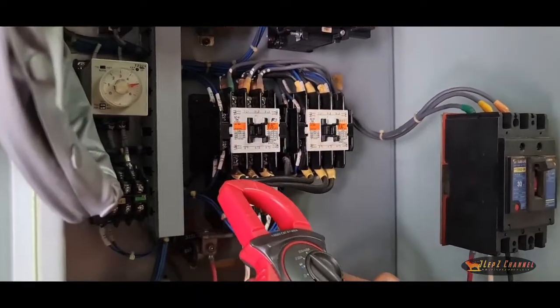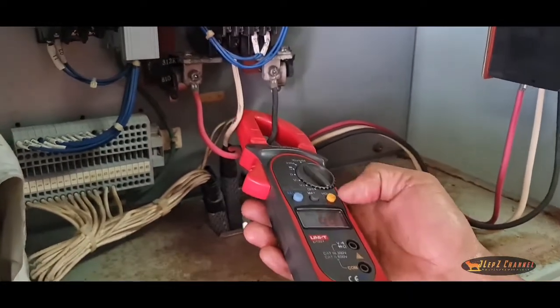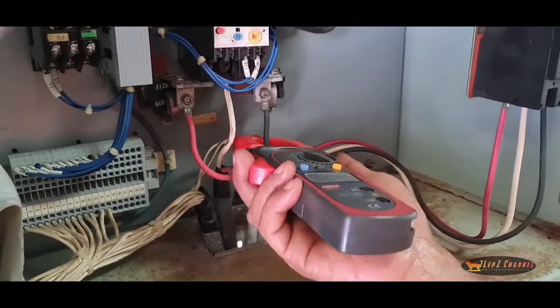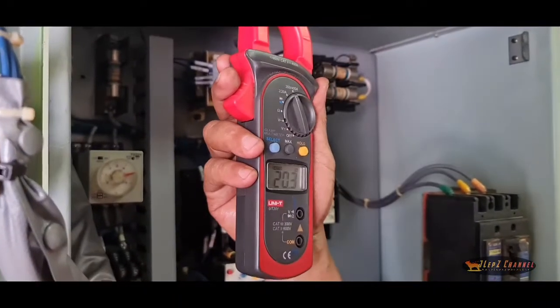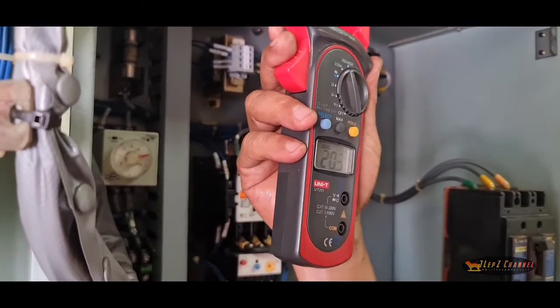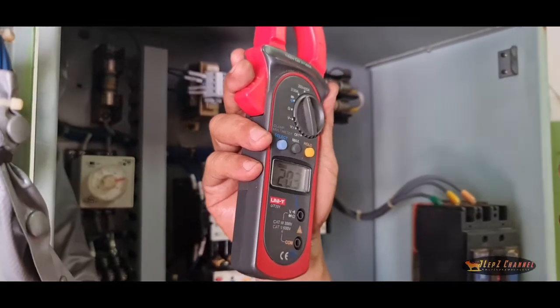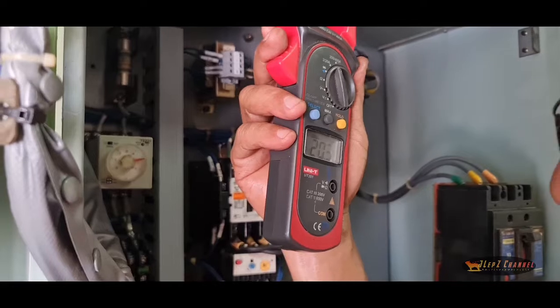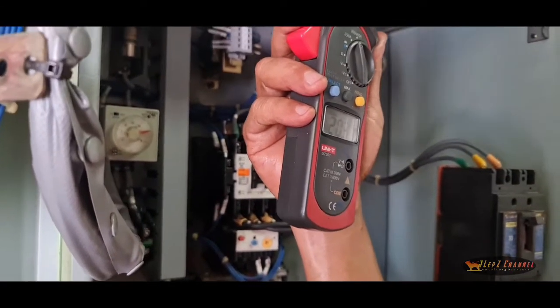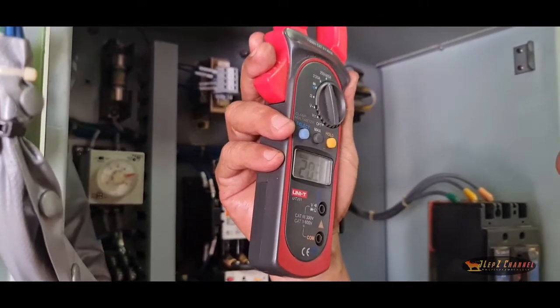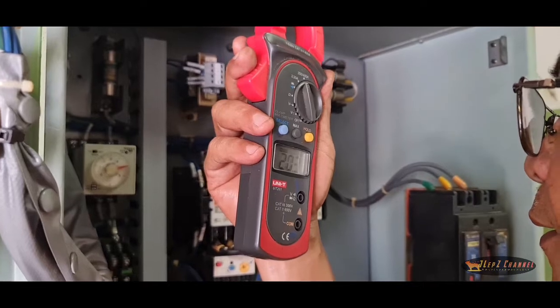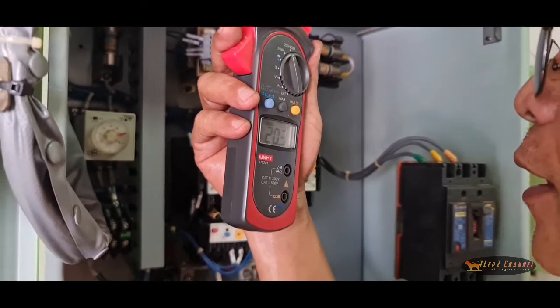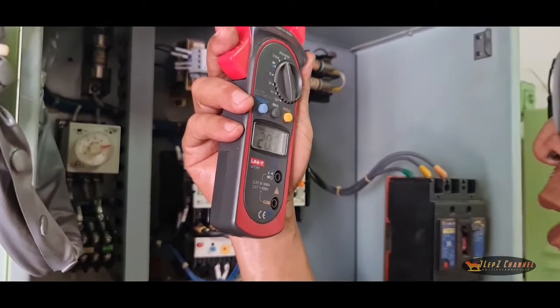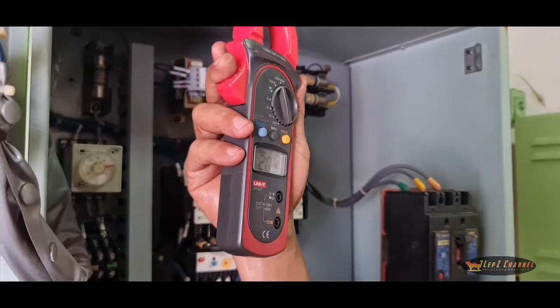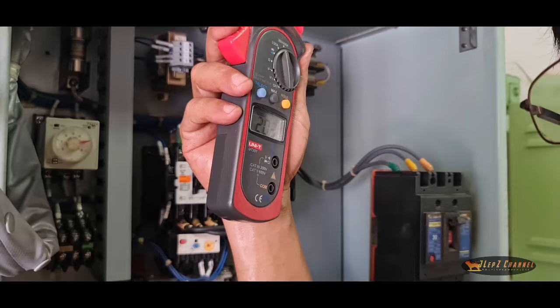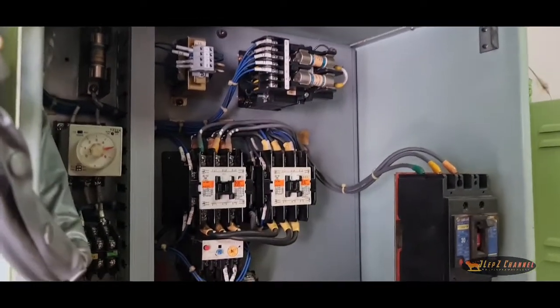Now I will release, then press the hold again. The line 3 current is 20.3. So you can see that the center wire, the line 2, has the highest line current. So to get our reference in setting the overload relay, we will get the highest as our average. So for safety purposes, we will choose the highest reading, which is 21.1.